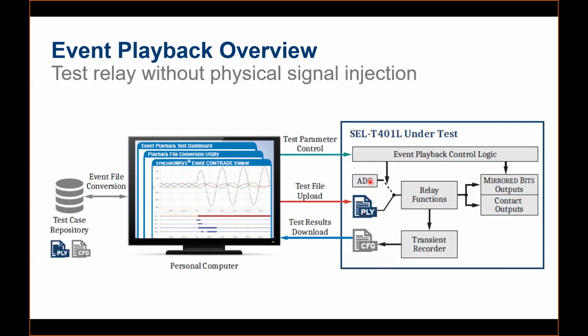So basically, it's using the real-time data, whatever the COMTRADE file you will load. The relay will internally change the path. Normally it's taking from the analog to digital converter, but then it switches to the COMTRADE file, whatever you load. So the relay uses the same physical values. That relay is a physical relay. You should have the physical relay with you.